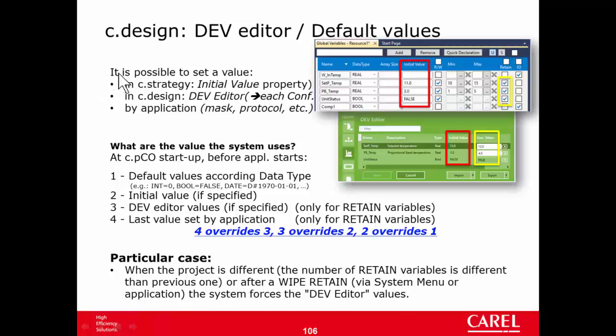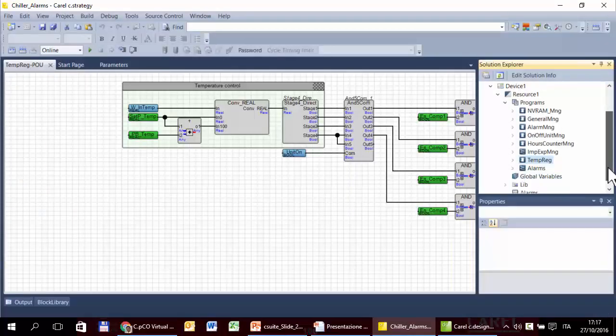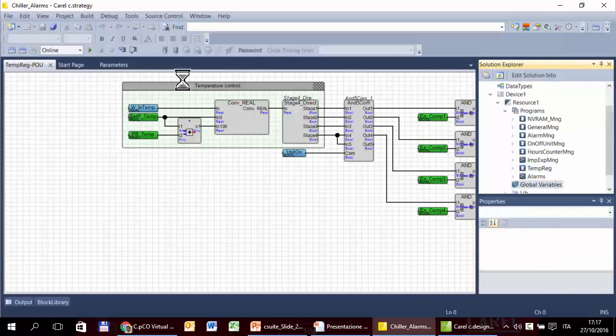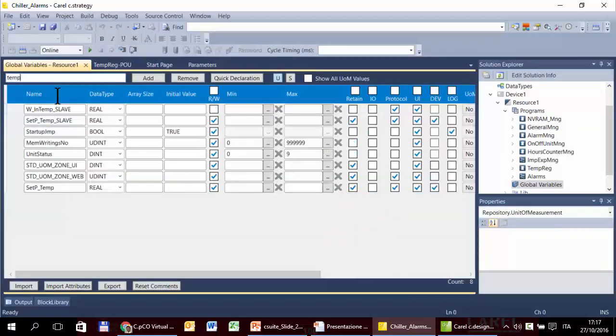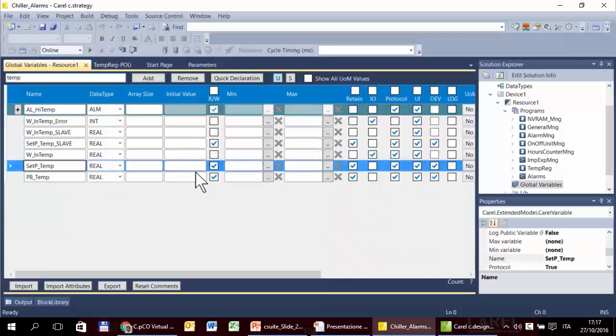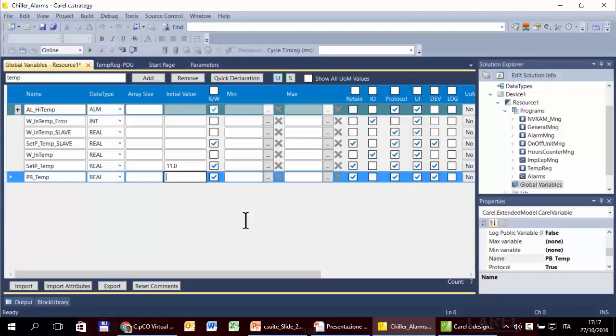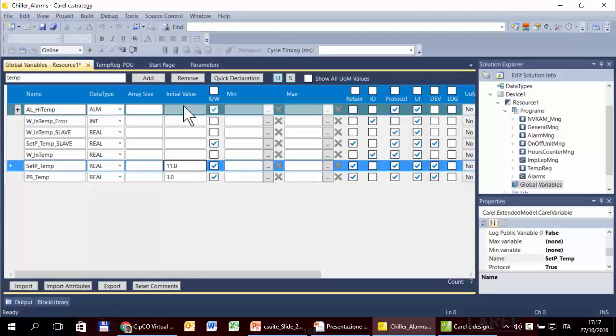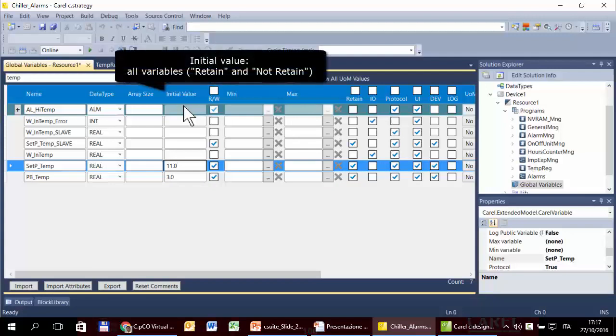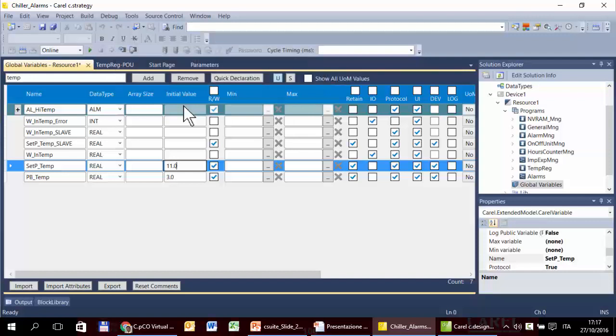How is it possible to change or set the value of a variable? The first option is in CSTRATEGY, using the initial value property — this column. We have CSTRATEGY; let's open the global or local variables. For example, for the setpoint we will set the initial value to 11, and the differential proportional band to 3. Please note that the initial value is available for all variables of the application — not only retain or volatile — according to other properties.